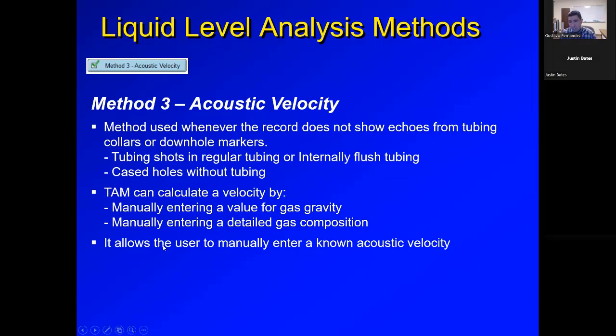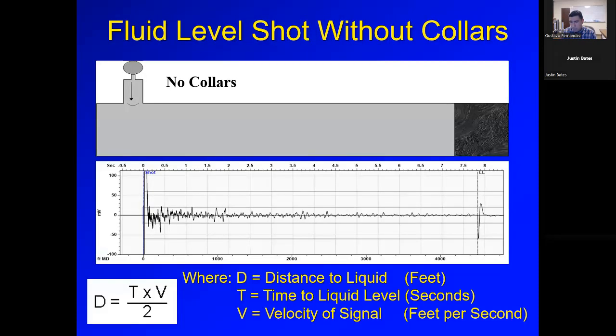As the last option, the user could manually enter the acoustic velocity. So we have studied a couple of methods to calculate the acoustic velocity, but even if we don't have a way to calculate it, the software still needs an acoustic velocity. So you can manually input that. The software will allow you to manually enter, and you tell the software what acoustic velocity you want to use for that fluid level shot. But that will be the very, very last option you want to use.